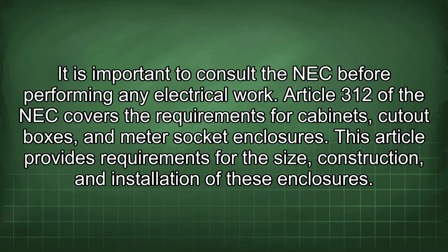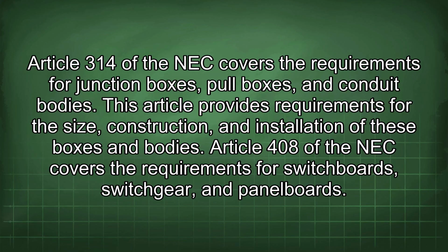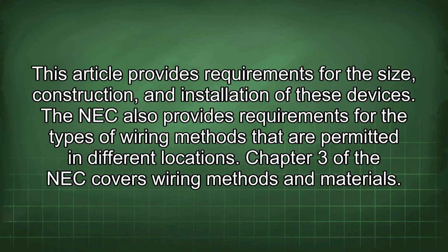Article 312 of the NEC covers the requirements for cabinets, cutout boxes, and meter socket enclosures. This article provides requirements for the size, construction, and installation of these enclosures. Article 314 of the NEC covers the requirements for junction boxes, pull boxes, and conduit bodies. This article provides requirements for the size, construction, and installation of these boxes and bodies. Article 408 of the NEC covers the requirements for switchboards, switchgear, and panel boards. This article provides requirements for the size, construction, and installation of these devices.